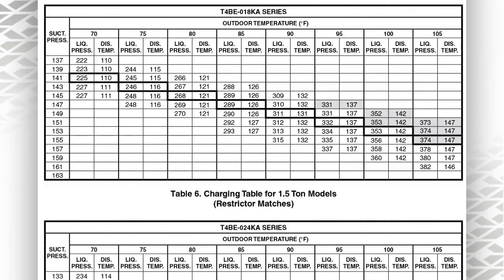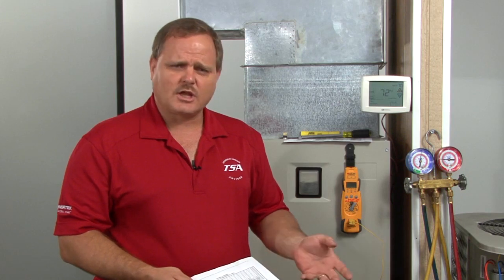If you have an indoor orifice, then you're going to use the charging chart that's referencing discharge temperature in the cooling mode. You could use a slide calculator doing wet bulb and dry bulb. You could use some of the charging apps that reference doing superheat and having the indoor wet bulb temperature. So that's kind of a whole other video topic, so I'm not going to get into depth with that.